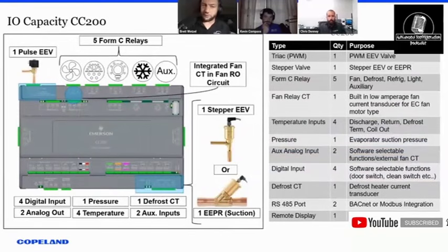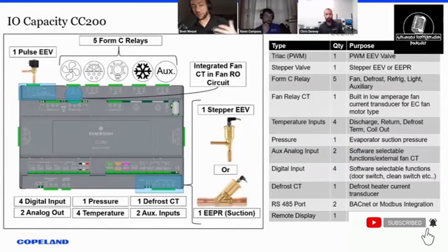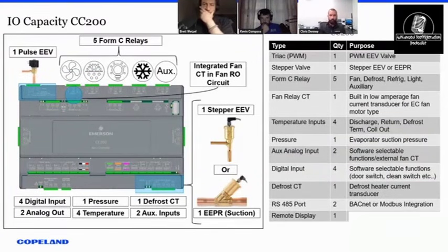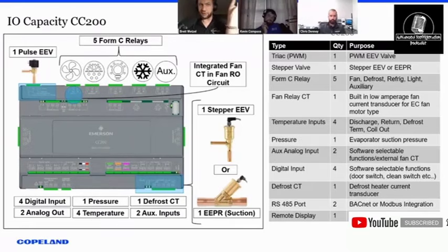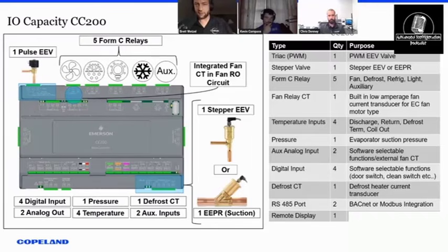So before you go off on that, I just want to ask a question. Is it an input that selects it, or is that something in the software? So right now it's done through E2 or E3. All right. So if it goes into EPTA mode, the controller internally can tell that case controller, hey, that medium temp is typically 6 to 8 degrees, but I want to knock it all the way down to 1 to 3 degrees. Exactly. Yeah.